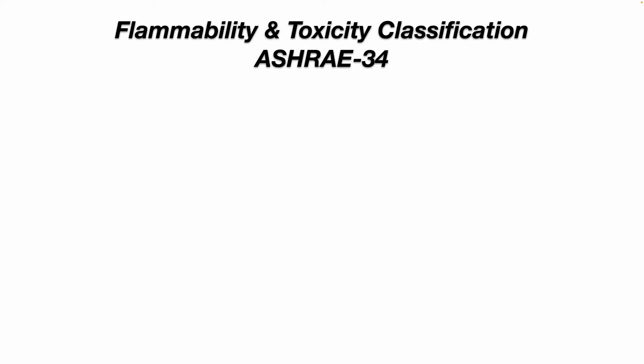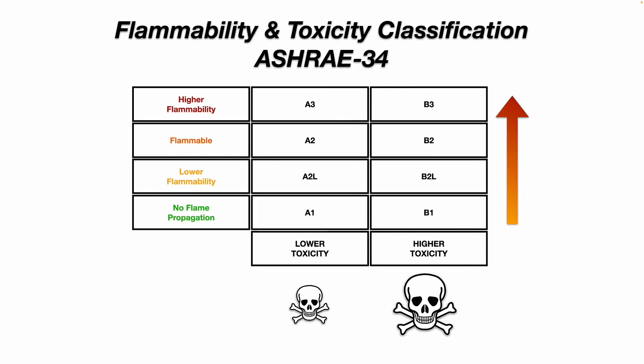Flammability and toxicity classification per ASHRAE 34 is another important chart to memorize. A1 refrigerants have no flame propagation. A2L refrigerants have lower flammability. A2 refrigerants are flammable. A3 refrigerants are highly flammable. B refrigerants have higher toxicity — think of it as A is okay, B is bad. A B3 refrigerant is both highly toxic and highly flammable. The higher the number, the higher the flammability. A is for lower toxicity; B is for higher toxicity.